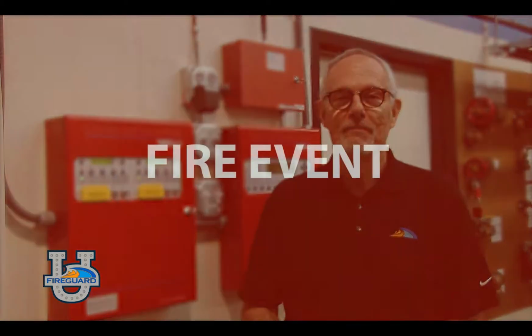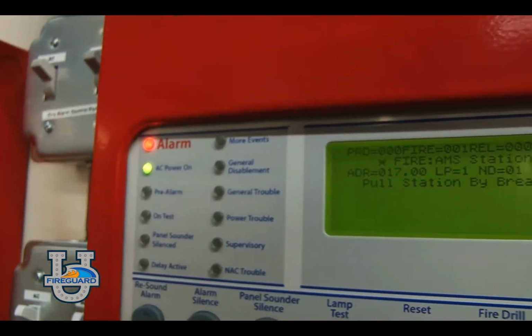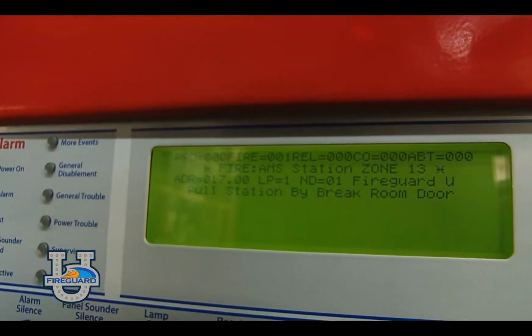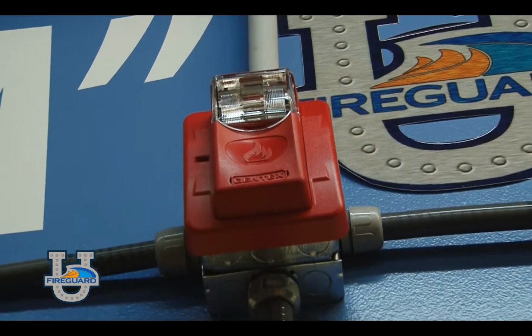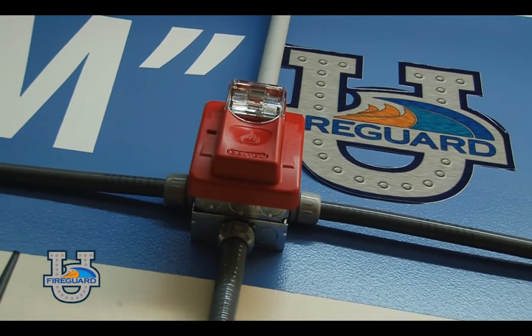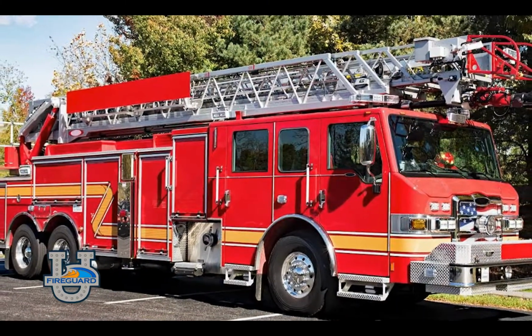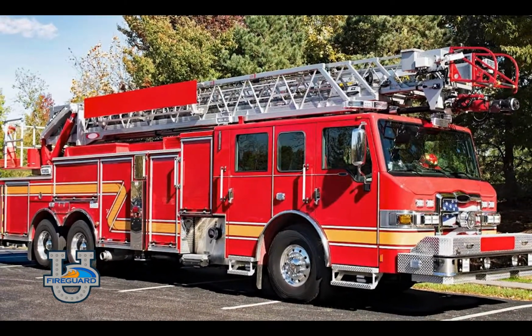Today, we'll be talking about fire alarm events and priorities, as they will appear on your fire alarm control panel. Most important, of course, is the fire event. The fire event will be indicated on your control panel by a red LED, and it is the highest priority, indicating a life safety hazard event. It activates the building evacuation signals and directly or indirectly notifies the fire department and responsible building personnel.